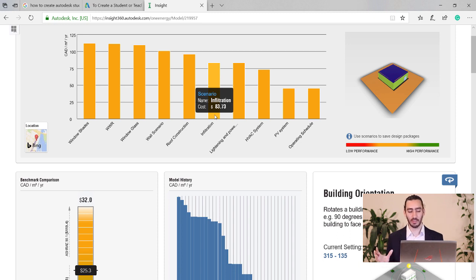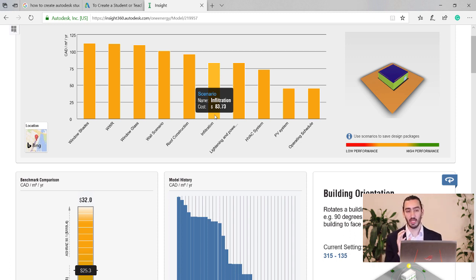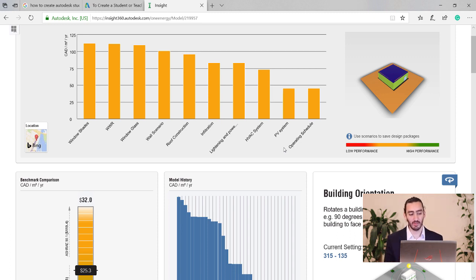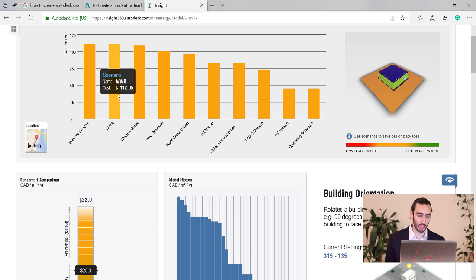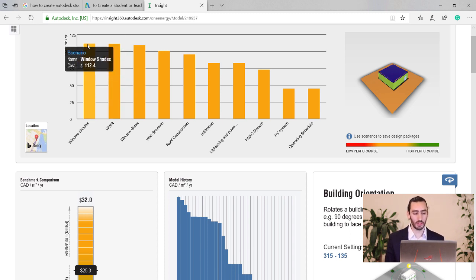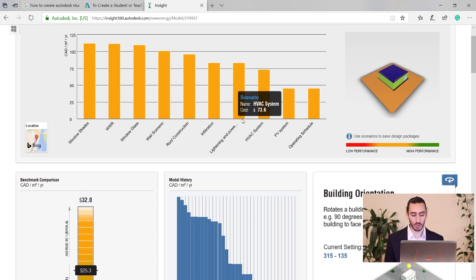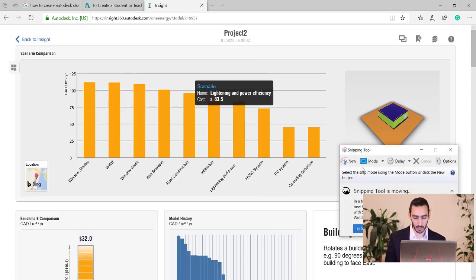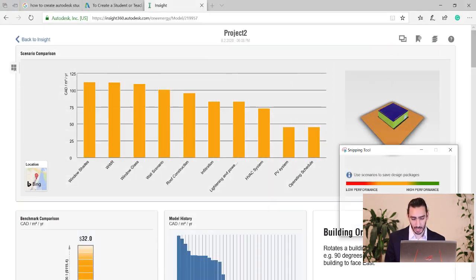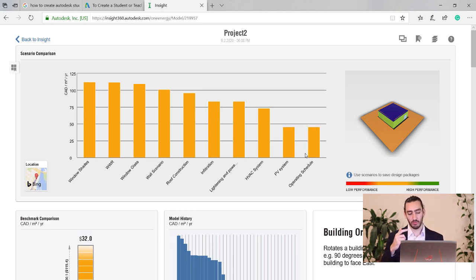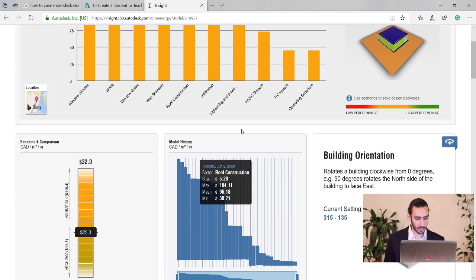If your budget is limited and you need to compromise, focus on the top two or three scenarios since they provide the most savings. Use the snip tool to capture these charts and save them for your report. You can see for wall-window ratios which walls had the most effect — northern and southern walls had the most saving effect versus western and eastern. Add all this information to your report template.